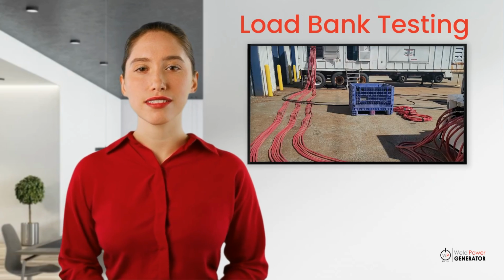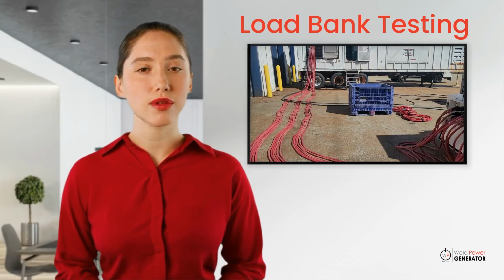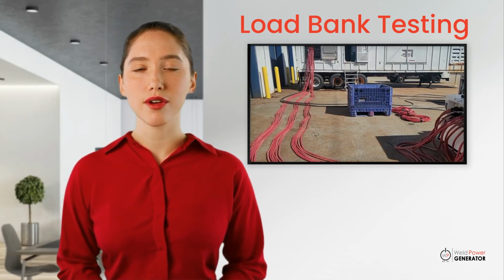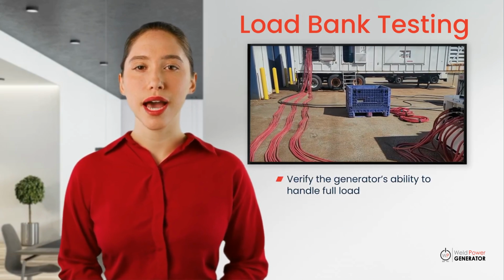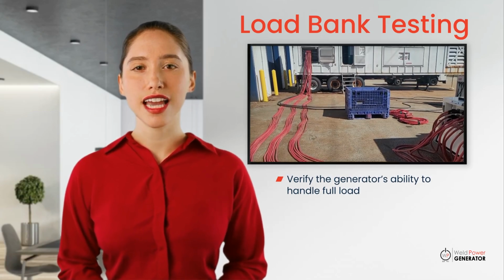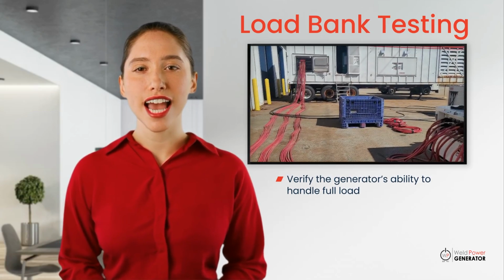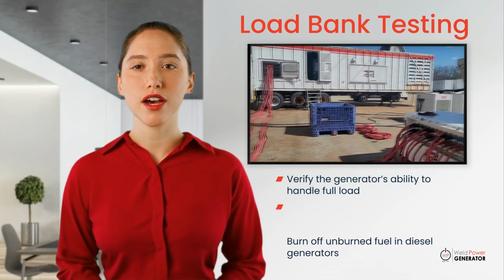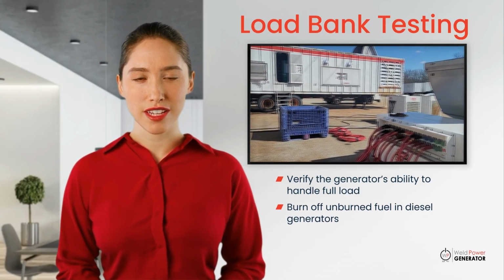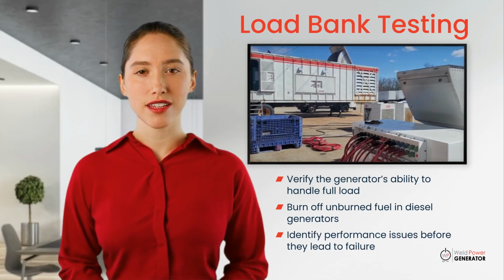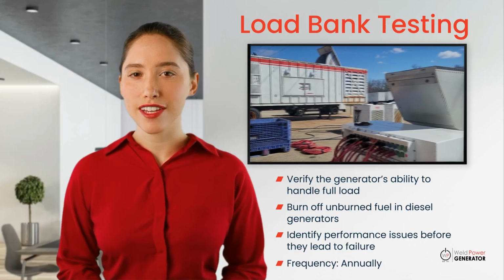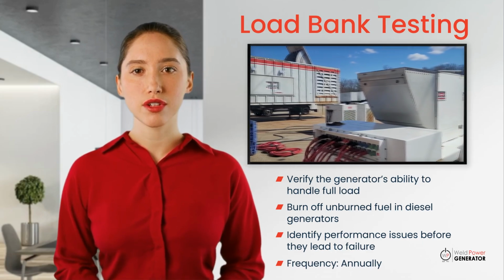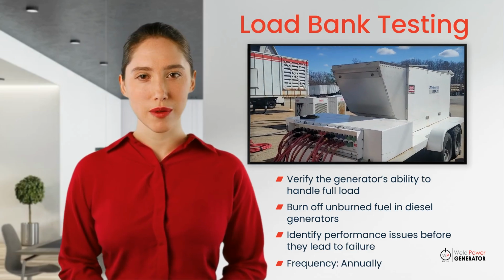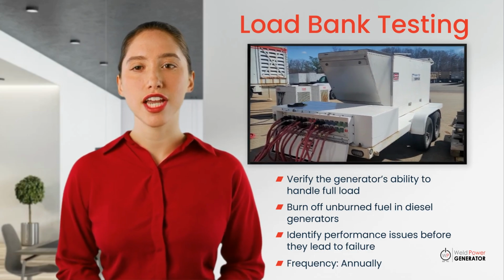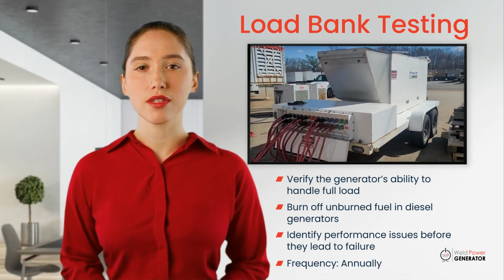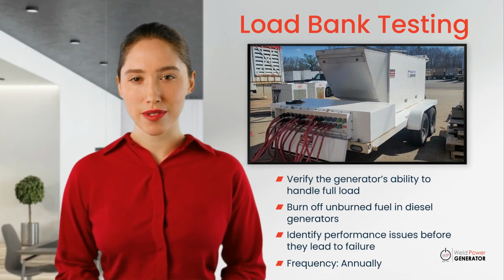A load bank test places an artificial load on your generator, gradually increasing the electrical load in specific increments until the generator reaches its full rated capacity in a controlled environment. This test verifies the generator's ability to handle maximum load and also helps burn off unburned fuel that can build up in diesel generators. This helps prevent wet stacking. Load bank testing is typically conducted annually for generators that don't often run under full load. A typical test lasts for 4 hours. Load bank testing ensures the generator's performance under peak conditions, which is essential for emergency readiness.